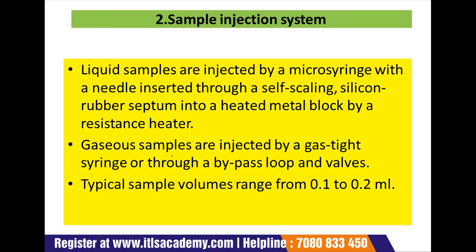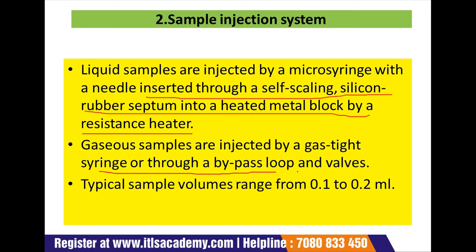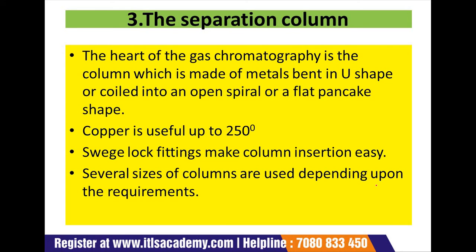In the sample injection system, liquid samples are injected by a microsyringe with a needle inserted through a self-sealing silicone rubber septum into a heated metal block by a resistance heater. Gaseous samples are injected by a gas-tight needle into a sampling tube, or through a bypass loop and valves. Typical sample volumes range from 0.1 to 0.2 ml.